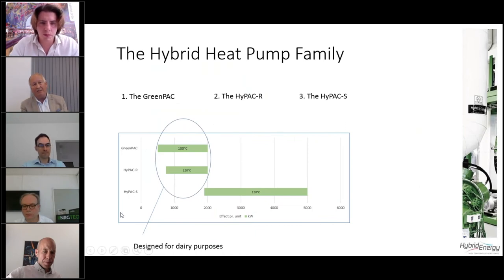Briefly about the hybrid heat pump family. The company was established in 2004, and today we have three basic products. The GreenPAC is a one-stage hybrid heat pump, delivers temperatures up to 100 degrees Celsius. The HyPAC-R is a piston-operated hybrid system, delivers up to 120 degrees Celsius, and it's a two-stage with two compressors. And then finally, we have the HyPAC-S. It's a screw compressor-based unit for larger capacities, up to 5 megawatts, and can also deliver temperatures up to 120 degrees Celsius. The two units I mentioned first are specially designed for dairy purposes and have a capacity limitation of 2 megawatts.